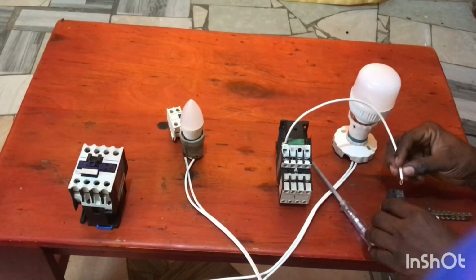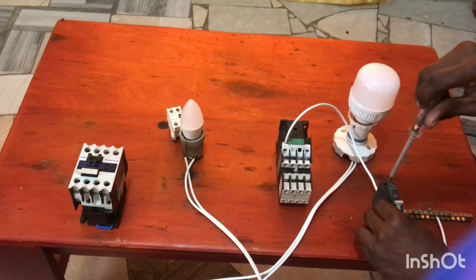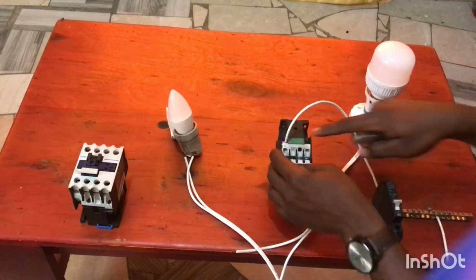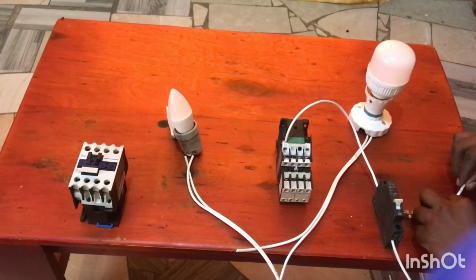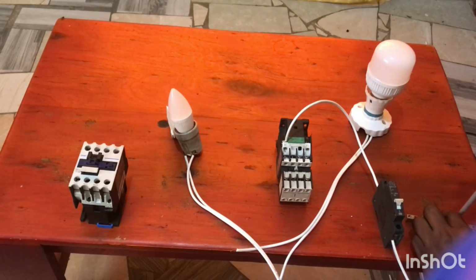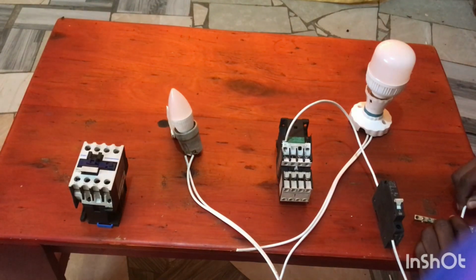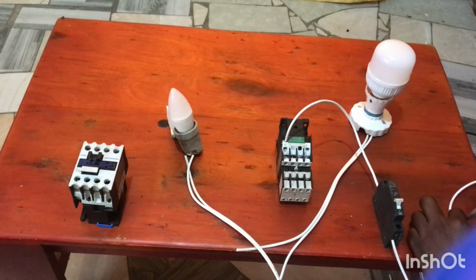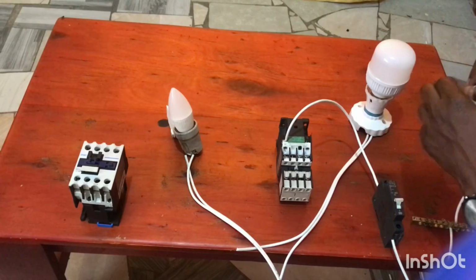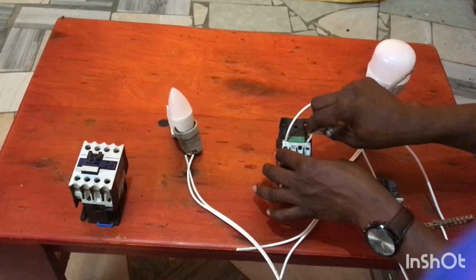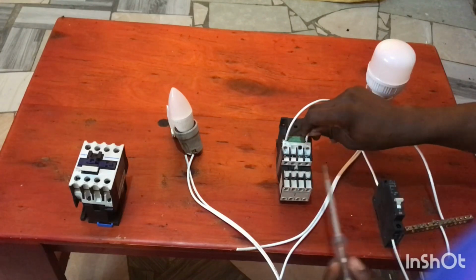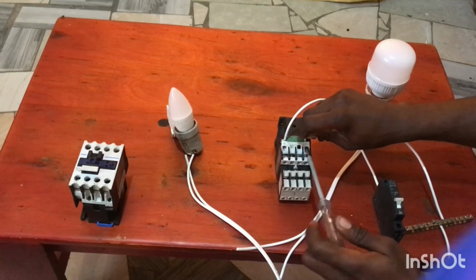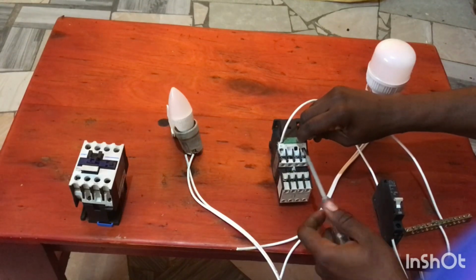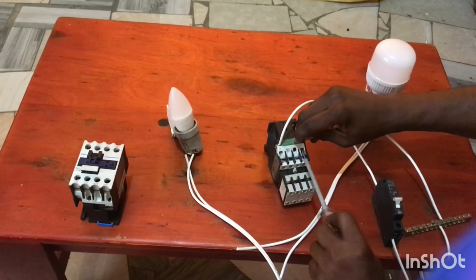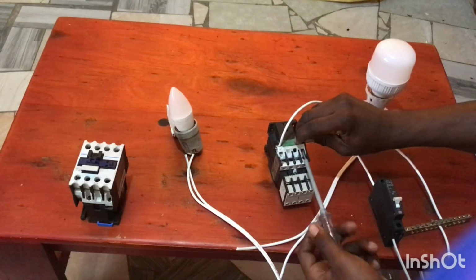So let me connect the contactor A1 and A2 respectively. A1 from the source, that's the live cable, and now I'll be connecting A2, which is the negative part of a contactor, from the neutral or the ground. So I'm putting the neutral at A2. By doing so, I'm done as far as energizing my contactor. The way it is here, it will be energized.